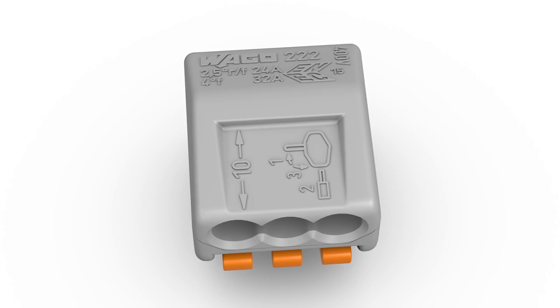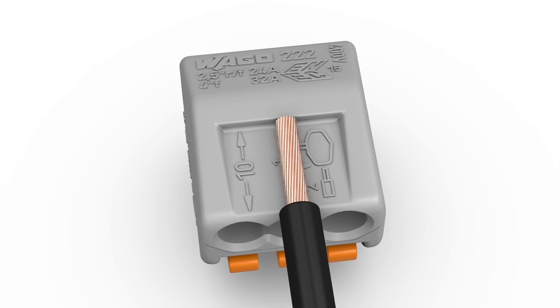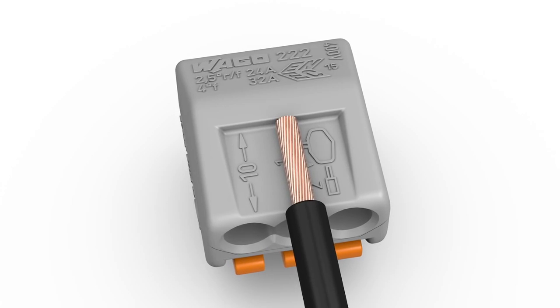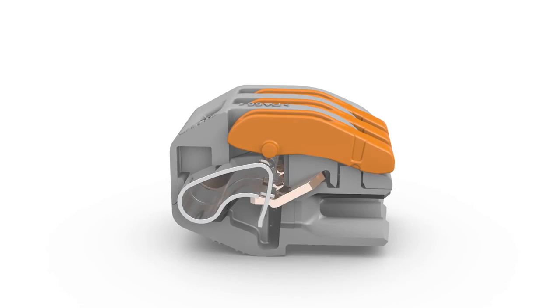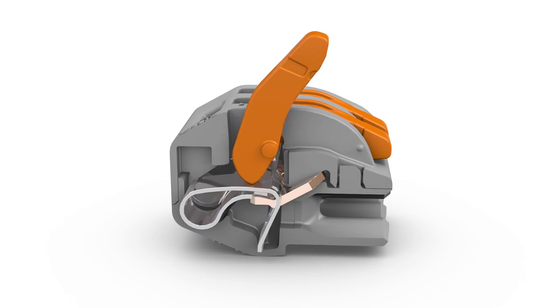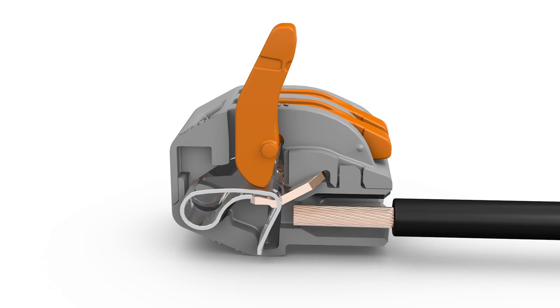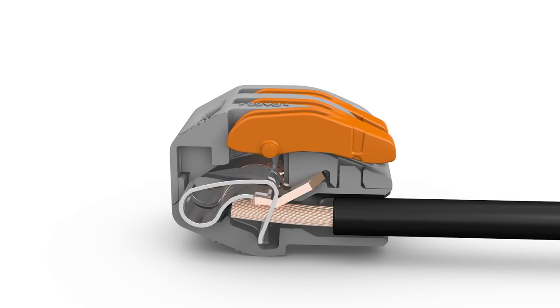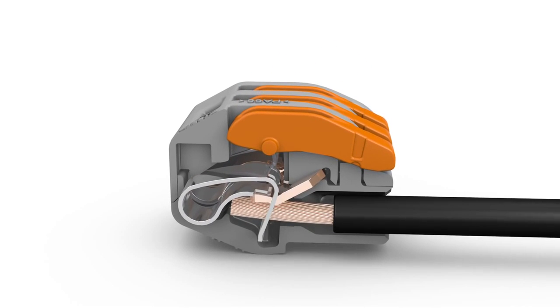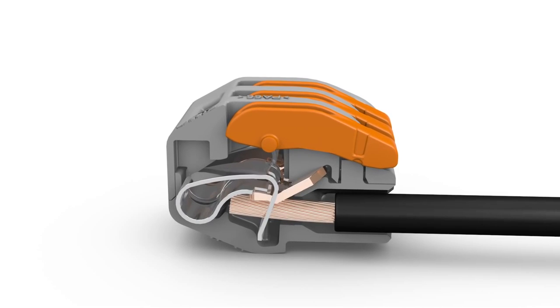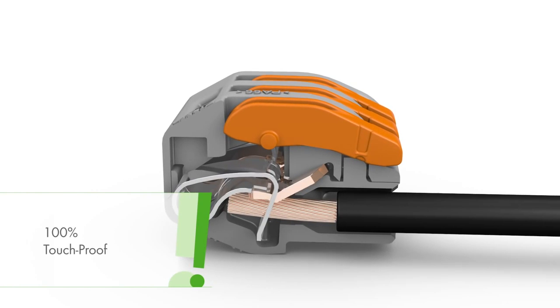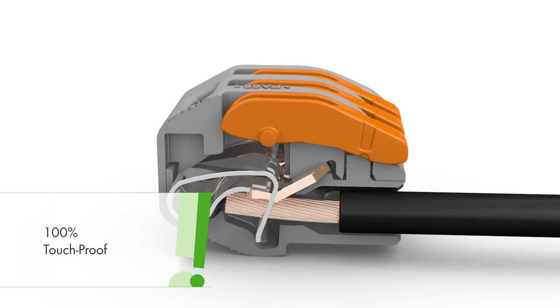Wiring is very easy. Strip conductor to 9 to 10 millimeters or 0.37 inches. Open clamping unit via integrated lever and insert conductor. Then lower lever to close the clamp. If properly terminated, the connector fully encloses the conductor insulation, preventing accidental contact with live parts.